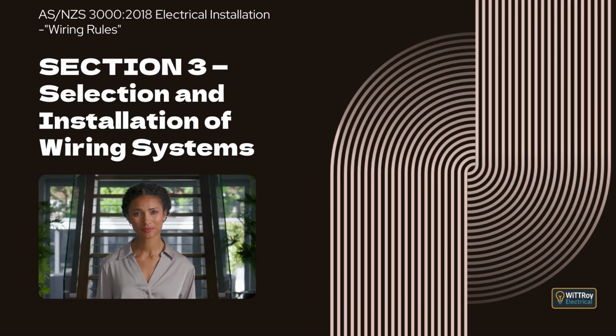Clause 3.7.2.9.2 Prohibited joints. This clause states that joints must not be made, when under tension, in certain types of cables including parallel webbed aerial cables, neutral screened cables, multi-core cables, or conductors of different metals. Clause 3.7.2.10 Underground cables. This clause explains that connections in underground wiring must be sealed to prevent moisture entry.